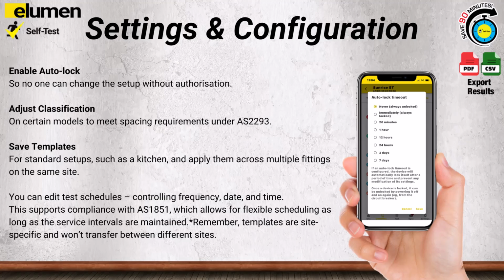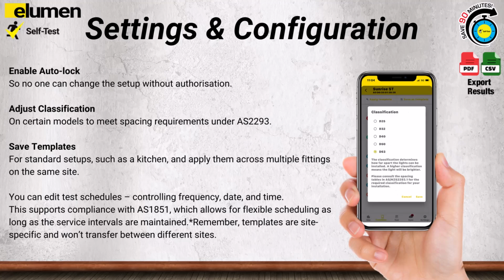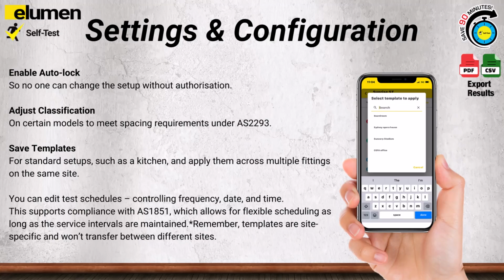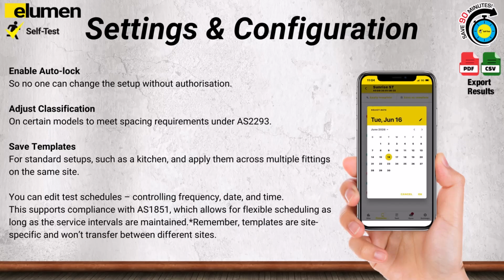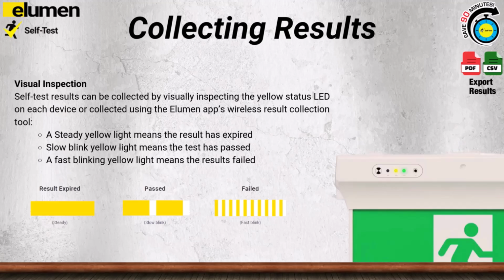Within settings, you can enable auto lock, so no one can change the setup without authorization. Adjust classification on certain models to meet spacing requirements under AS2293. Save templates for standard setups, such as a kitchen, and apply them across multiple fittings on the same site. Remember, templates are site-specific and won't transfer between different sites. You can edit test schedules, controlling frequency, date, and time. This supports compliance with AS1851, which allows for flexible scheduling as long as the service intervals are maintained.